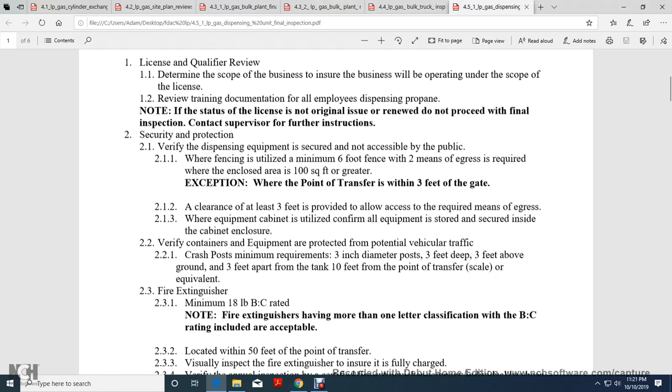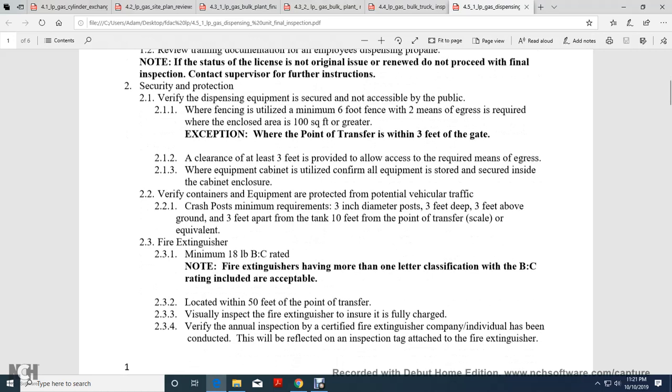Verify containers and equipment are protected from vehicular damage. Posts shall maintain minimum requirements: 3-inch diameter post, 3 feet deep, 3 feet above the ground, 3 feet apart from the tank, 10 feet from the point of transfer (scale) or equivalent. Fire extinguisher: minimum 18 lb. B:C rating. Fire extinguishers with more than one classification B:C rating are acceptable, located within 50 feet of the point of transfer.